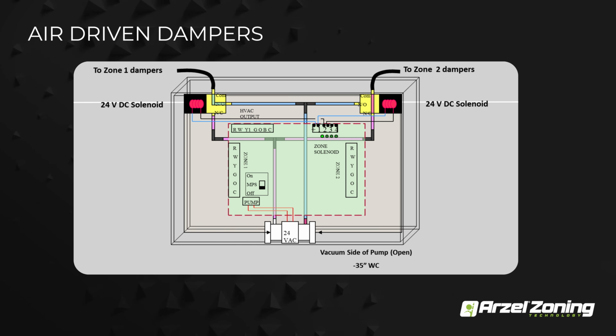So very simple, really reliable solenoid. And this here is just a picture of the inside of the panel box, so you guys can take a look at the bottom there. The pump is in the bottom white piece. It says 24 VAC written on it. The pump wires are going to go to the pump terminal on the board, and you're going to see that there's a pressure and vacuum tube that leave the pump, and each of those are going to go into the solenoids themselves. Then it depends on the call whether it's going to be open to the vacuum or pressure side of that pump.